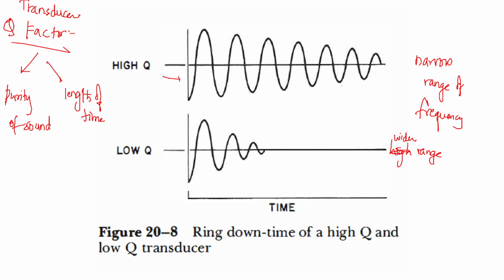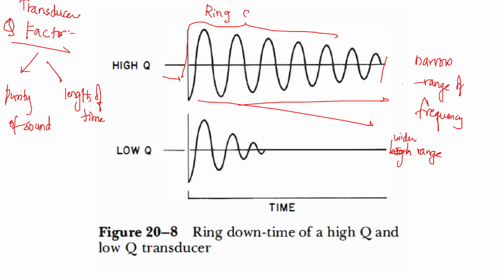So these high Q transducers vibrate for a longer period of time. The interval between the initiation of the wave and the complete cessation of the wave is called the ring down time. And this ring down time is more for high Q transducers, whereas it is less for low Q transducers. So Q factor will tell us about the purity of the sound and also the length of time for which the sound is present.